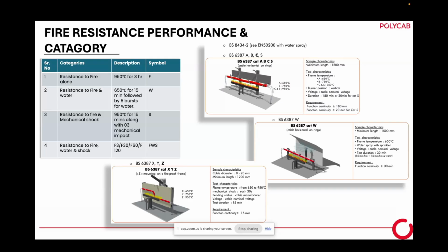Also, the cable is exposed to water, so rapidly, fire and water occur. Since it is a huge fire, there is a chance of heavy material falling from the top into the cable, causing mechanical shock. So the cable experiences fire, water, and mechanical shock together. With these three criteria, the fire survivable cable has to work, and even while experiencing fire, water, and mechanical shock, the circuit integrity should remain intact.